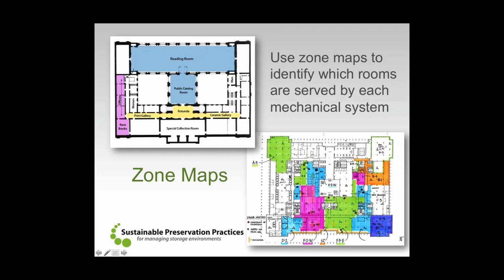And you start to find all of a sudden that, well, here we go, this zone that happens to be served by A3 is the name of the mechanical unit. Well, some of A3's air goes up here, but some of it also goes over here. And did we realize that? And in this particular physical zone, here's my wall surrounding this particular perimeter. As we start looking within that room, we realize all of a sudden, even though this is just one physical space, now I've got 1, 2, 3, 4 different air handling units that are serving a portion of that physical space. So as you walk through the room, on one particular spot, we may be in A3, and over here we might be looking at D2 or F2W or whichever mechanical system that might be.